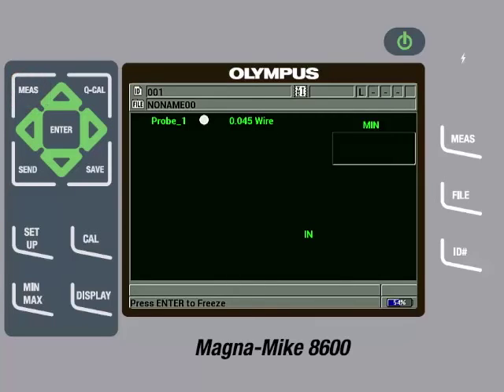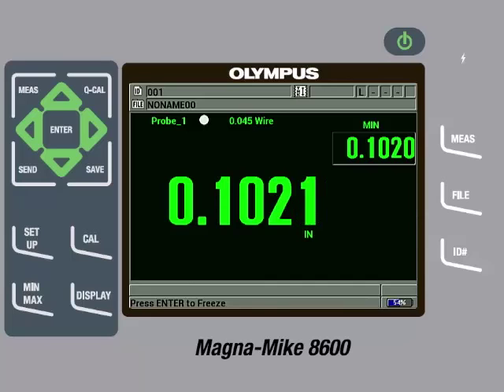We can now insert the wire target into the cooling hole of the turbine blade and place the thicker side of the turbine blade on the probe tip so the gauge is measuring the distance from the probe tip to the wire target and displaying the thickness of the turbine blade. At any time, we can press the Measure key to reset the captured readings. We can scan along the length of the part and also rotate the part. The minimum thickness will be updated as we scan.